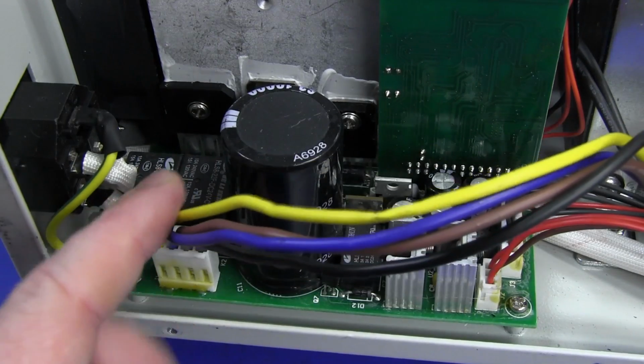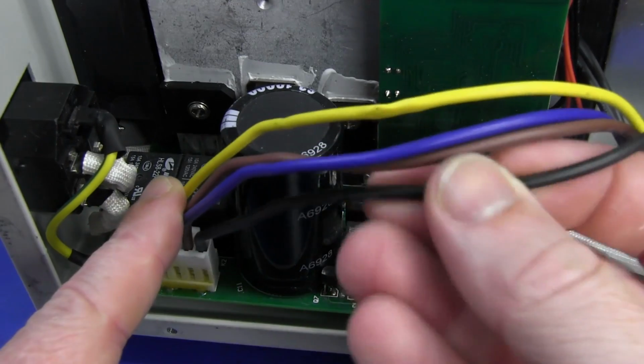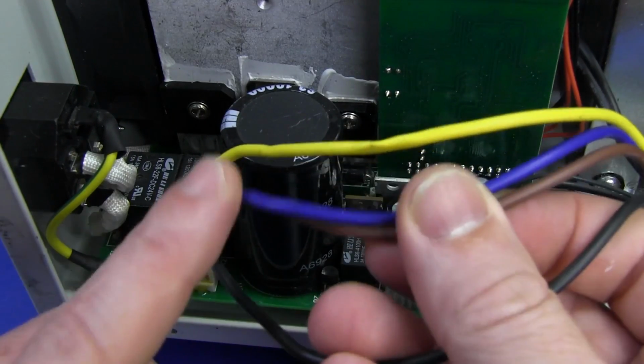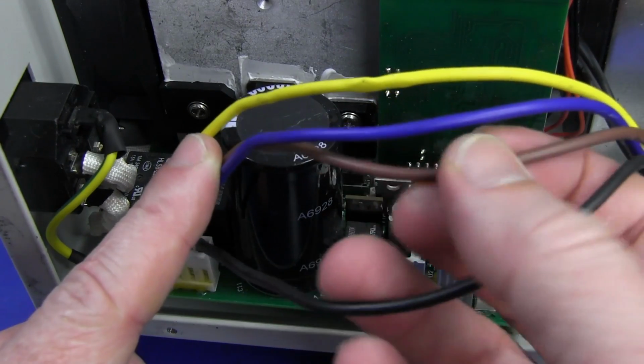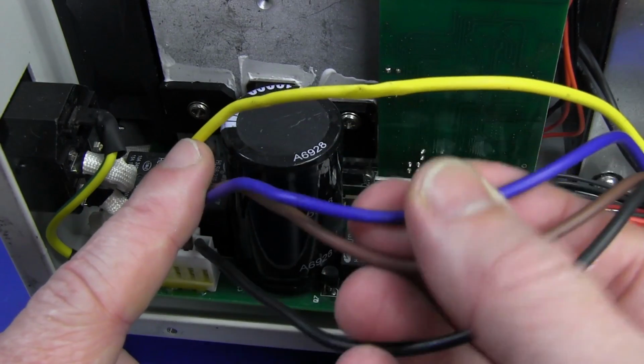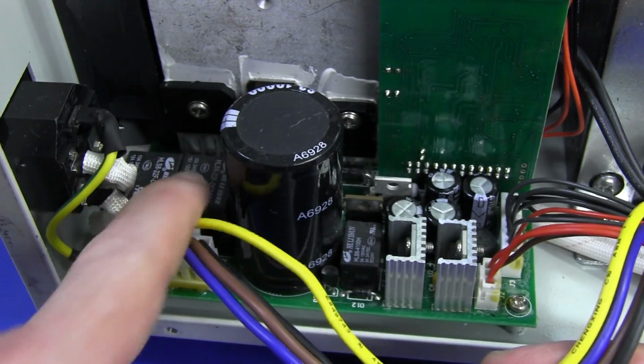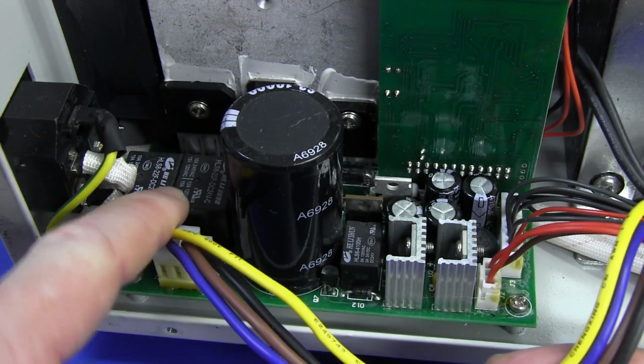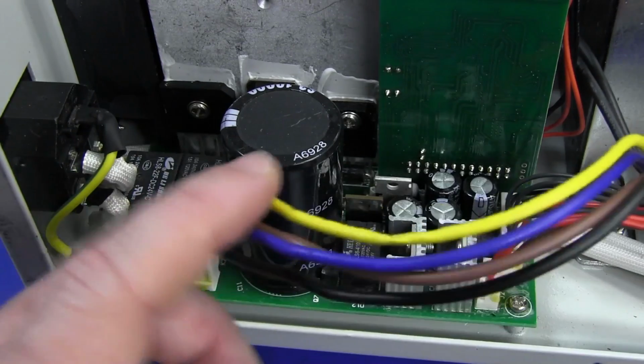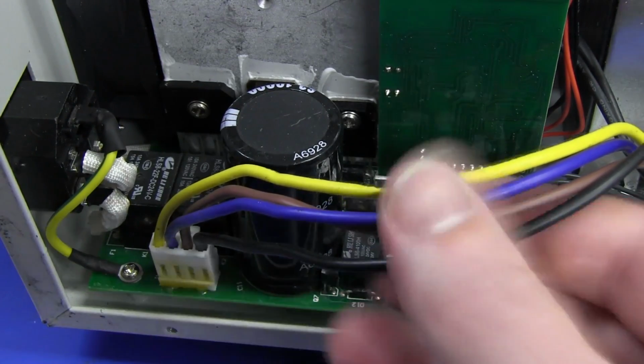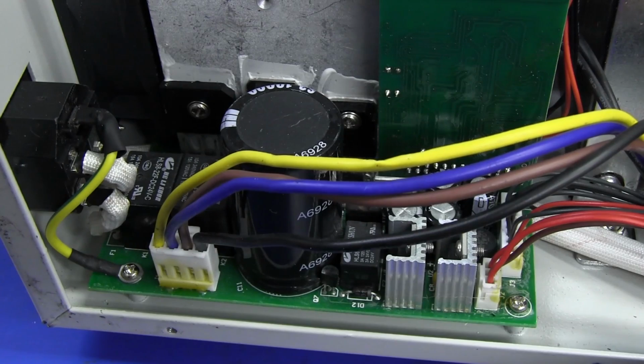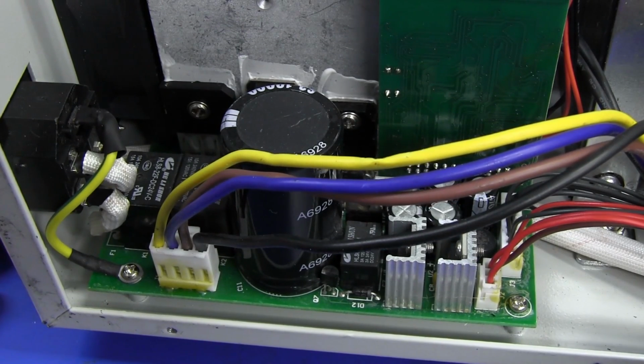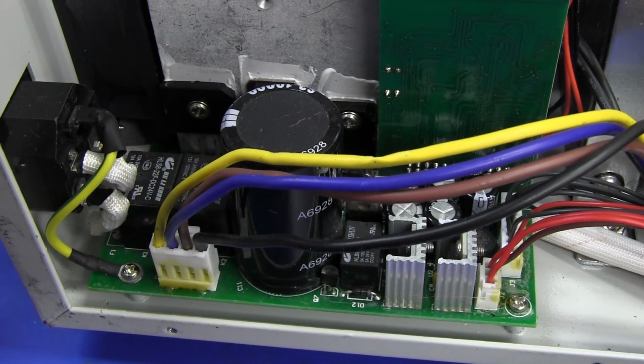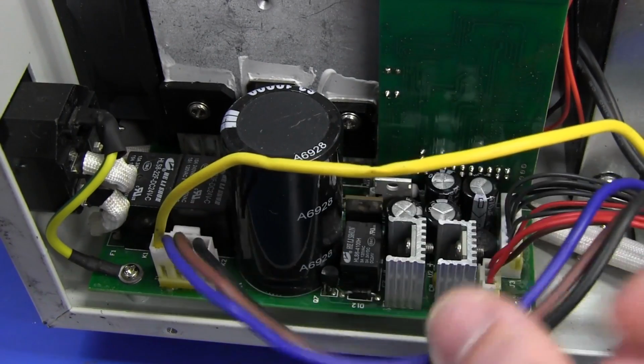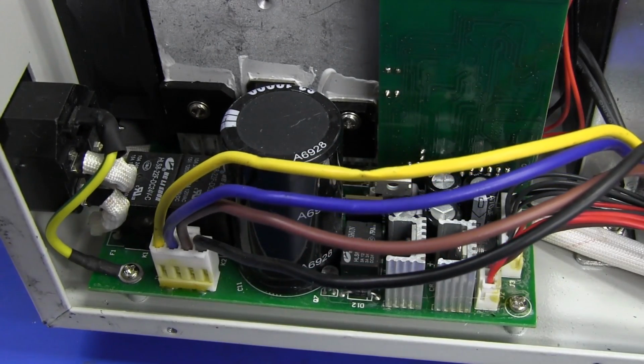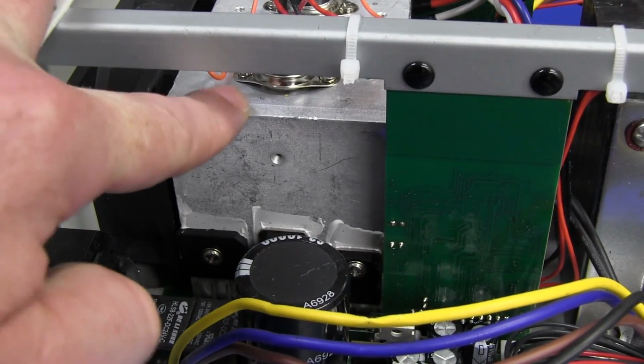So let's look at the one individual channel we've got here. Here are our 3 input taps. So here's our common, and we would have our 7.6 volts, our 19 volts, and our 34 volt taps. And there are the 2 relays down in there to switch between those various taps. The reason that you have taps like that in one of these linear power supplies is because if you've got one at 34 volts for your maximum output voltage capability, and you've got 5 amps output current, whoa, you're going to be dissipating a huge amount of power in your heatsink.